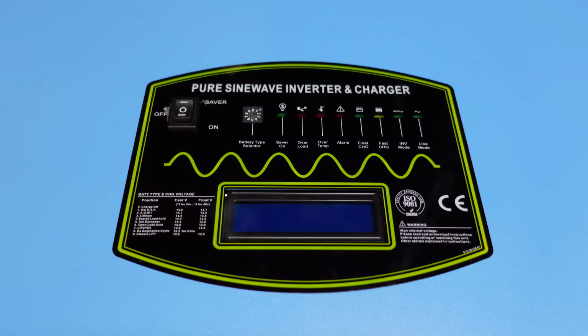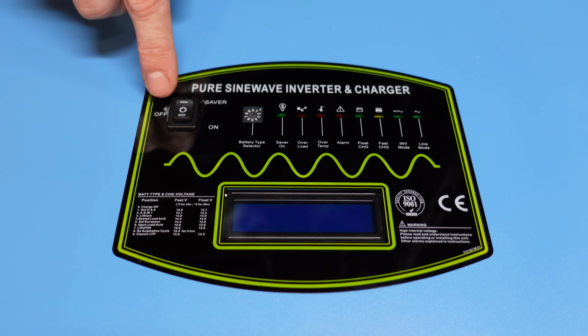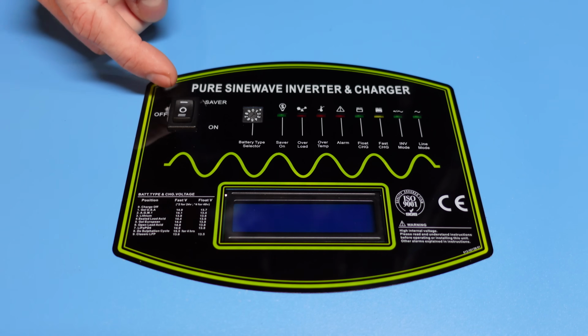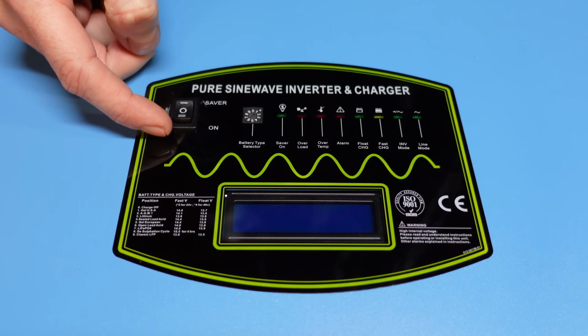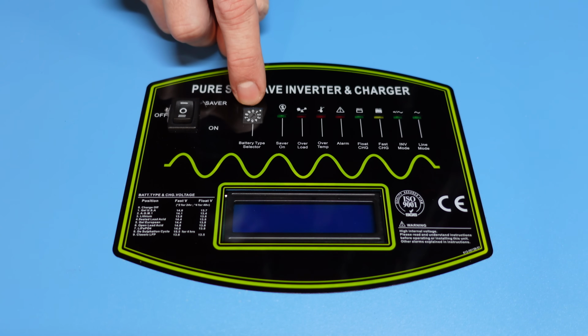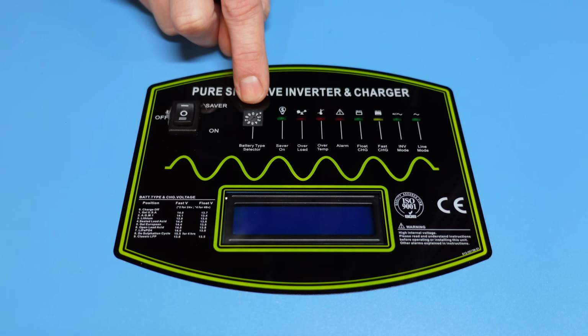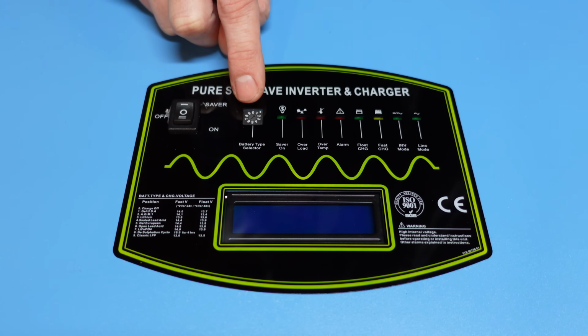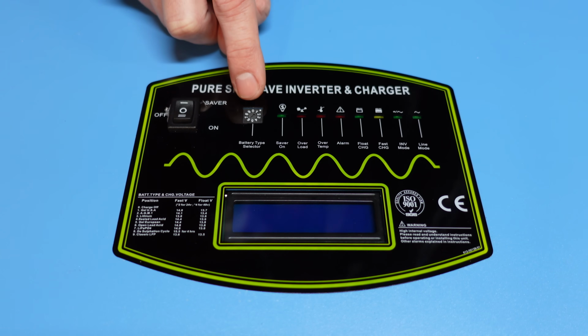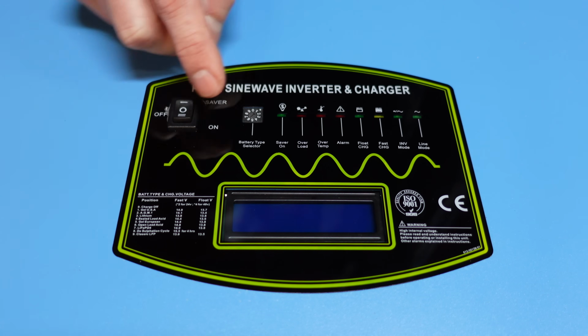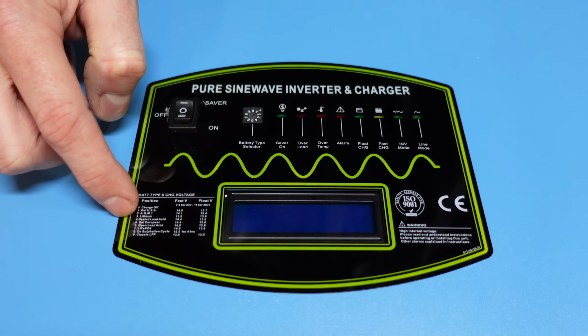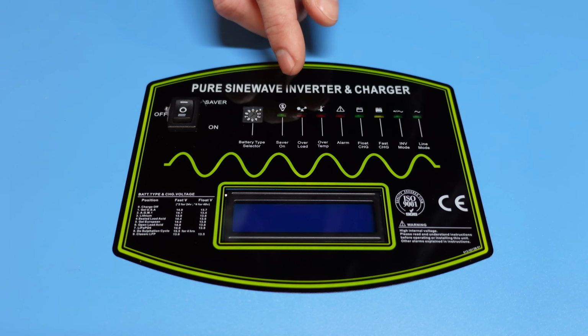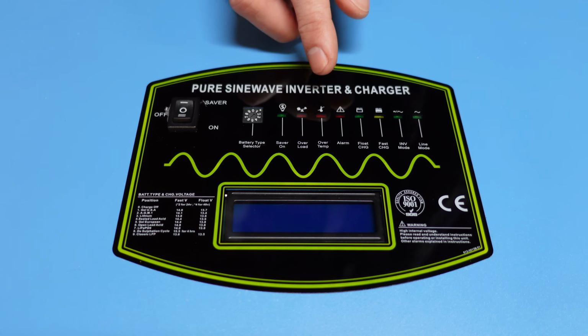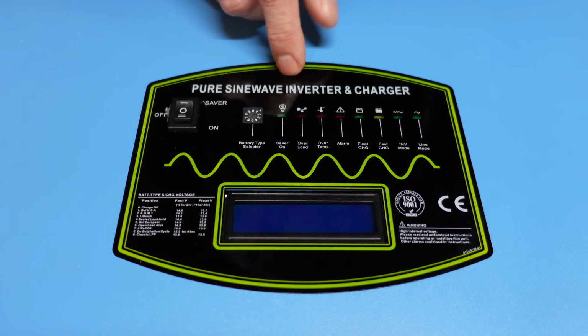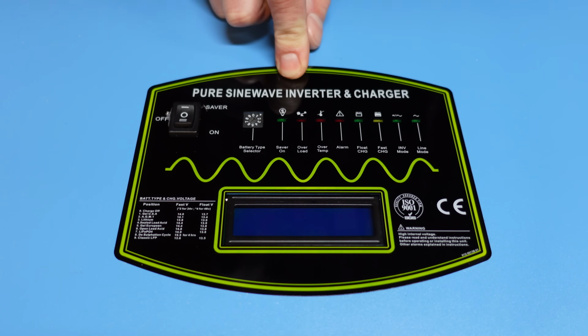Let's see. So taking a look at the front of the inverter first here, we have the on-off switch. The center position is off. Turning it up is power saver mode and turning it down is on. We have a battery type selector. This inverter is a newer model that does support lithium iron phosphate, which is pretty cool. It also supports various versions of lead acid, gel, sealed batteries. There's actually a chart over here which will help you with that. And then various status LEDs to determine the state of the inverter, as well as any fault codes that may have occurred. It's a fairly standard LCD and control panel for these types of inverters.